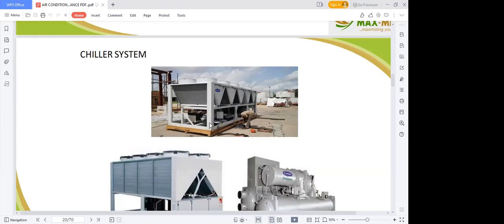You don't need any other unit except the chiller with some ducted units, with air handling units, pumping the cool air within the space. Areas where this might be needed include shopping malls, a stadium, a museum. And not Nigerian, because I've been to a museum here in Lagos, so I'm not talking of that kind. I'm talking of a big museum, those types you see in Europe. We talk of a theater, the National Arts Theatre, where you have more than 500 people viewing a program at the same time. You need it in a church. Some bigger churches also have chillers. And big halls for weddings, if you can afford it, you go for it.